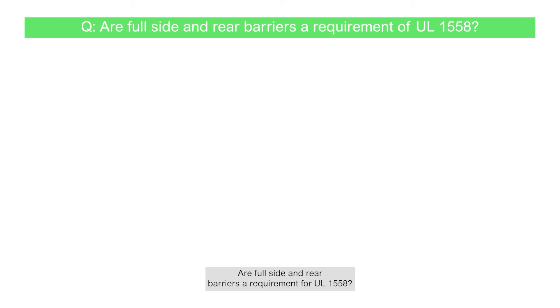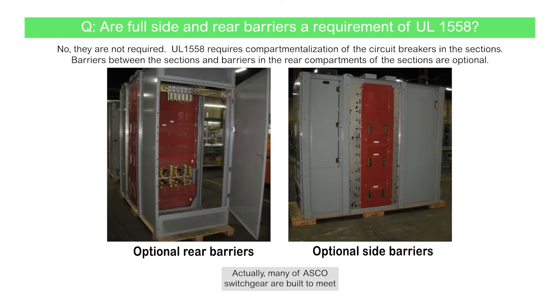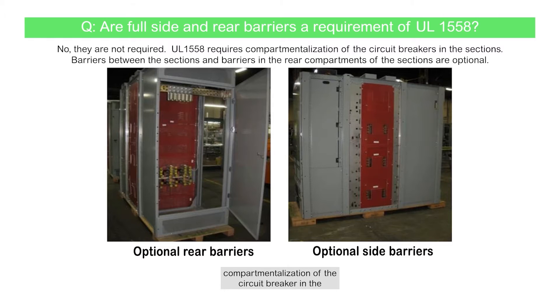Are full side and rear barriers a requirement for UL1558? Actually, many of ASCO switchgear are built to meet the UL1558 requirements. The UL1558 requirements call for compartmentalization of the circuit breaker in the sections, but it is not required to have side barriers between sections or rear barriers at the rear of the sections.